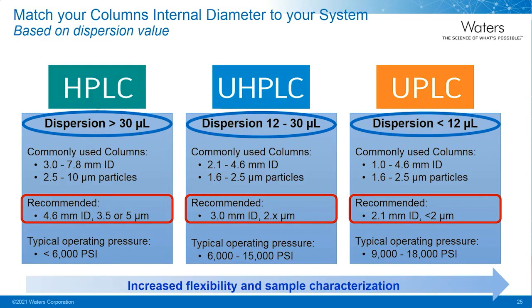A column with 3.5 and 5 micron particles can be used on HPLC systems, while the 2.x micron particle columns are appropriate for UHPLC systems. And columns with sub-2 micron particles should be used on a UPLC system to gain the best efficiency and best resolving power.